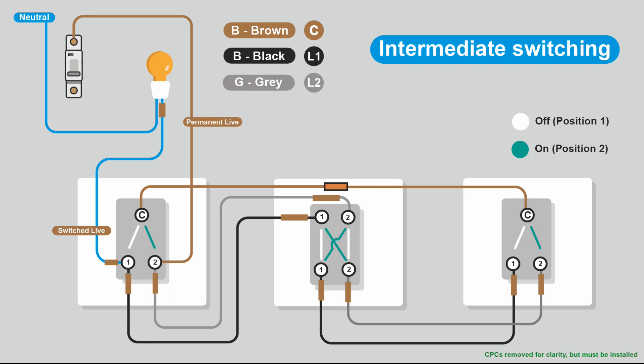When you've got lots of conductors and a multi-gang switch, it helps to know which are the permanent lives and which are switch lives. There are no set rules on which colours go to which connections - BBG is what I like to use, though some people use black for the common. Again, it's important to sleeve them. Whatever way you choose to connect your strappers, stick with it - it'll make things much easier. If you keep changing your mind every time you do lighting, you've always got to keep checking what you've done at the other switches.